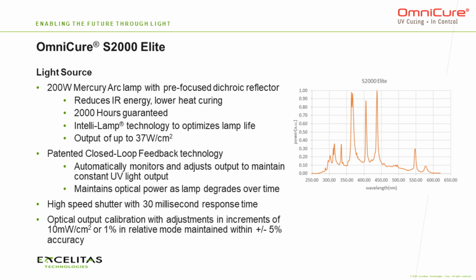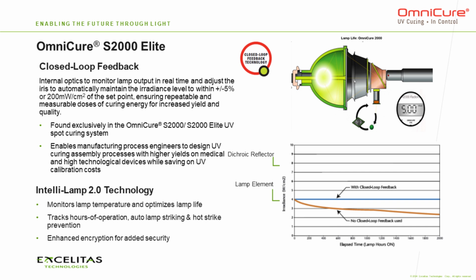As I mentioned earlier in this presentation, the patented closed loop feedback technology really allows us to monitor the output of the system and just maintain it over time. So it automatically adjusts for any slight variations, which is really, really important in terms of having an accurate and repeatable process. It also has a high-speed shutter, the Elite does, with a very fast response time, and also the ability to calibrate the system, which is also very important for this application. If we look at the lamp a little bit in more detail, you can see over on the right-hand side in the graph what happens with closed-loop feedback in terms of output and what happens if you don't have closed-loop feedback. So you can appreciate the importance of that particular feature.